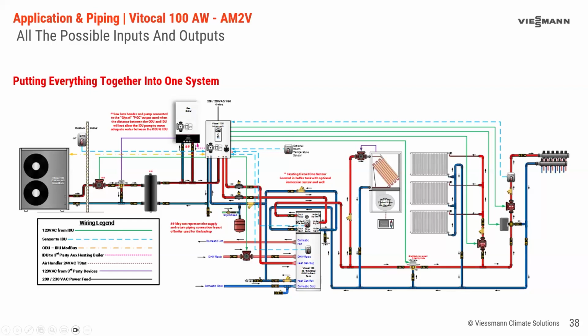And then I want to leave it here because we had a great question earlier, which came in anonymously, and that's quite all right. Will the indoor unit pump still circulate if the backup boiler is piped directly on the buffer tank, from an operating standpoint? I did answer yes. If there's a call for heat or chilled water, regardless of what there's a call for, the indoor unit pump operates. I'm assuming it's because we were talking about DHW and piping that backup boiler that we're looking at here, not directly to the buffer tank.